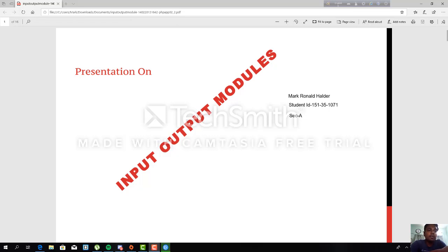There is another thing, and that is the discrete input status table word. 16-point discrete input modules are assigned to one word in the input status table. A 16-point discrete input module residing in slot 3 would be addressed as I:3.0, bits 0 through 15.